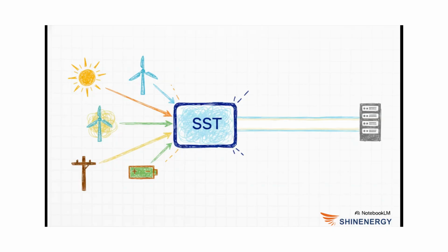Well, the real magic lies in something called multiport power aggregation. If you just use a solid-state transformer to do a basic, simple AC to AC replacement of an old transformer, you're kind of missing the point, and it just adds unnecessary cost and complexity. The real, game-changing advantage unlocks when you use an SST to intelligently aggregate multiple, diverse power sources at the exact same time, acting as a dynamic, high-speed buffer for those violent AI power spikes.